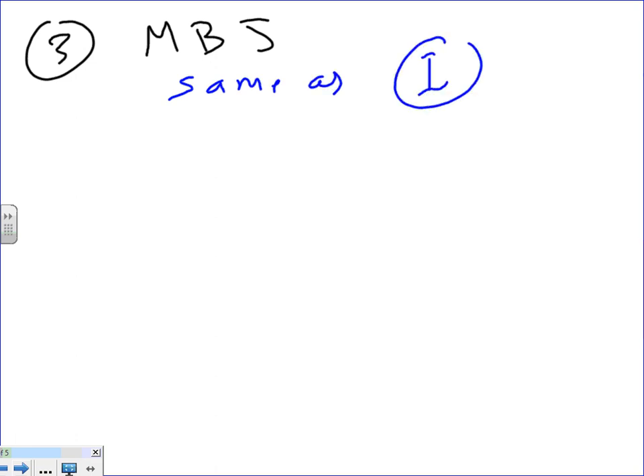Number 3, guys, is the main bonding jumper. It bonds the grounding bar in the switchgear to the neutral bar, or the grounded bar, in the same switchgear. So we size it the same as number 1, with some exception. Do you guys remember? Same as 1, but here's the big but.